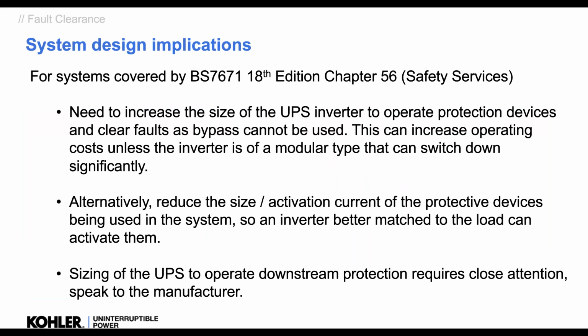We should always use the smallest device downstream that we can. Don't stick with the typical 32 amp type Cs, go for the smallest breaker. And we have to be very sure that the UPS can do it. We see an awful lot of incorrect sizing of UPS. It doesn't work on UPS as you would expect to trip circuit breakers. We are very confident. We've sorted all our UPSs out with circuit breakers in our workshop. We fully understand how things work. I'm very confident we can trip circuit breakers. And if you come along with one we haven't tested, we're very happy to test that as well.